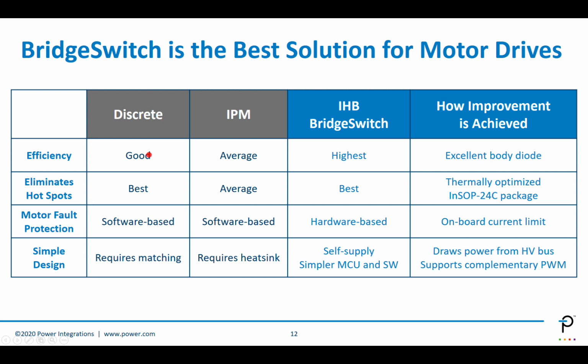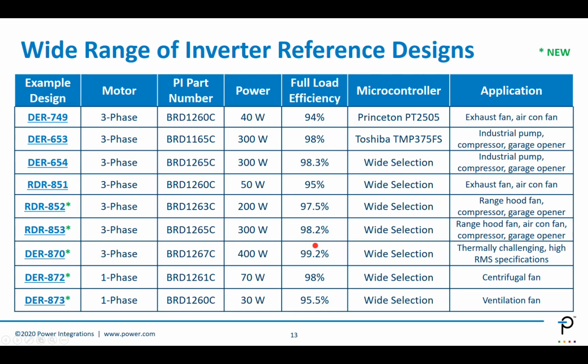Against the discrete, BridgeSwitch offers higher integration, doesn't require matching, and has a hardware-based motor protection, with minimum external components compared to the discrete. There is also a wide range of inverter reference designs, which are suitable for many applications. As you can see here, we have single-phase designs. We have a lot of three-phase solutions based on the different part numbers, covering different power levels from 30 watts to 400 watts.